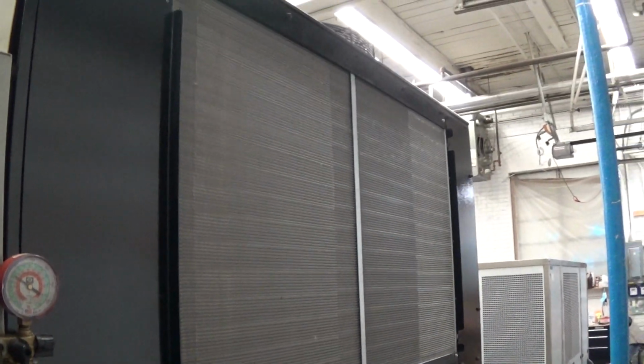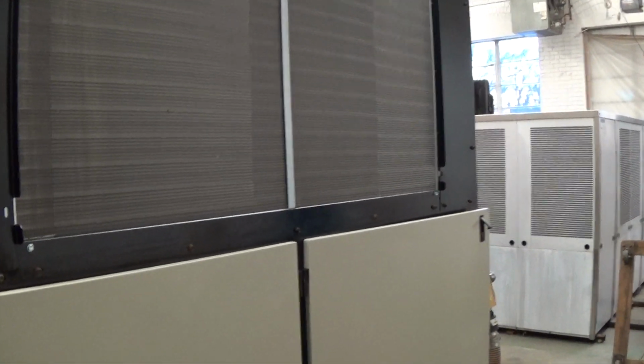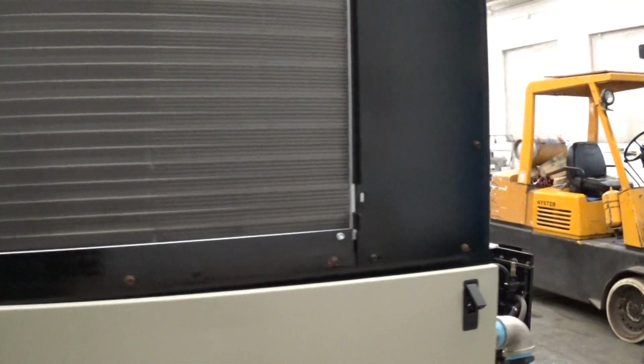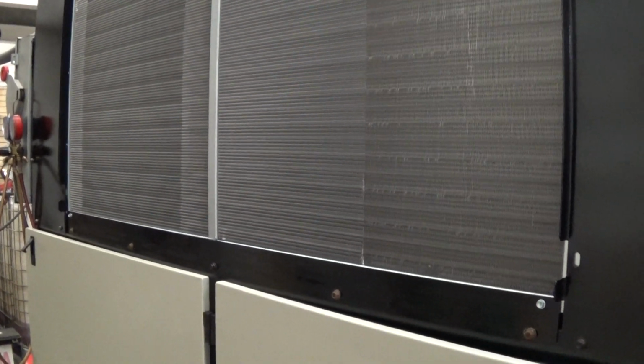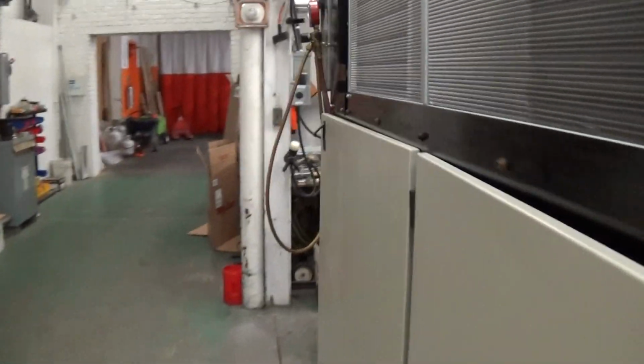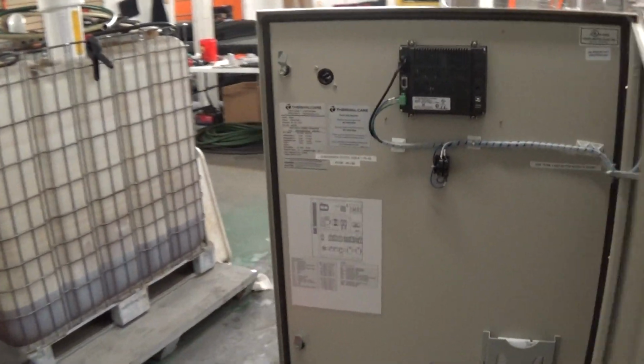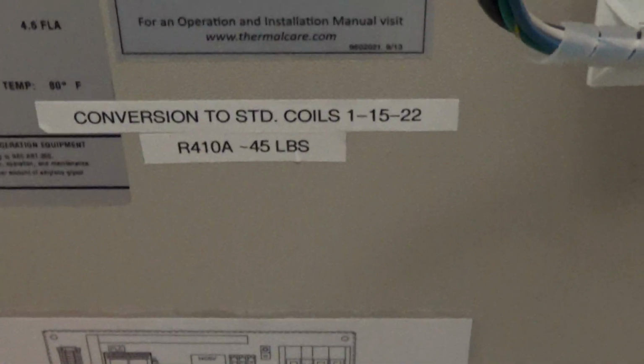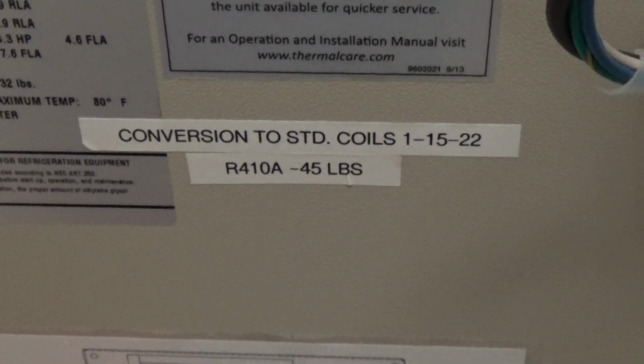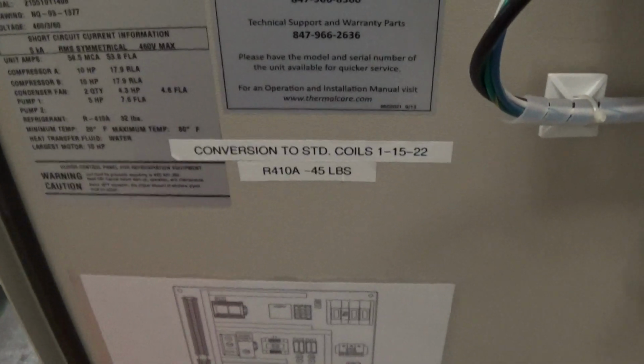What does that mean? That means right around 2012 is when people were coming out and using micro channel coils, which have been improved drastically, but they had some fallbacks, disadvantages, repairability if they developed a leak, which this chiller had when we got it. So we put on two brand new, more robust, conventional coils. Took some work, took some money, but in doing so, they do use more refrigerant, and any chiller HVAC tech will tell you that's normal. So it uses about 45 pounds of R410A, which is in there now, and it's going to ship fully charged.